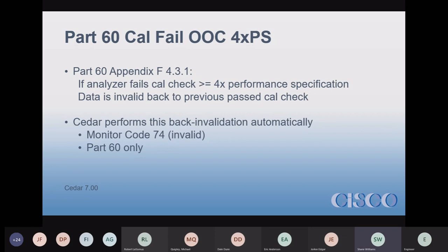There's a monitor code for data substitute, like 40 through 51 or 52 or something. So if we change that monitor code to data substitution, it was for part 60 reporting, to calculate it correctly. I believe it still counts those as downtime. Brian just chimed in to answer Dave's question: the substituted data monitor codes are still considered invalid monitor codes and are downtimes. So that's the answer.